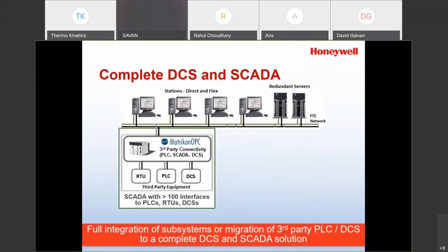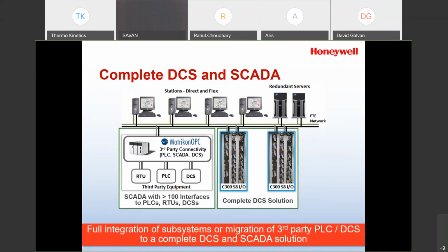You can connect all the systems together, up to 11 systems together, and as much as you need. But one cluster can handle 10,000 process tags. Just to give you the differences here, one cluster of Experion PKS can handle 50,000 process tags. So just keep that in mind. But it's a full DCS complete solution. Same tools as Experion, same HMI web builder display graphic design, same library containment, same function blocks, same integration into everything. The only difference is that you do not have universal I/O capability with Experion LX as you do with PKS. But you can integrate a UOC into an Experion LX architecture, or you can integrate a PLC that has universal I/O to accomplish that.